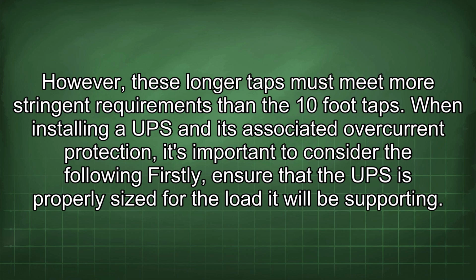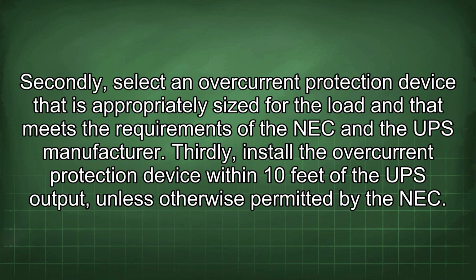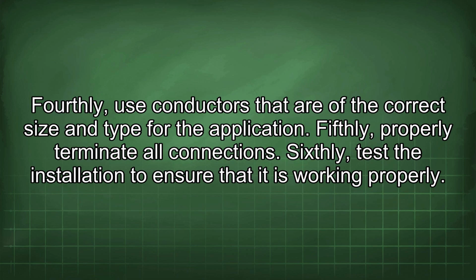When installing a UPS and its associated overcurrent protection, it's important to consider the following. Firstly, ensure that the UPS is properly sized for the load it will be supporting. Secondly, select an overcurrent protection device that is appropriately sized for the load and that meets the requirements of the NEC and the UPS manufacturer. Thirdly, install the overcurrent protection device within 10 feet of the UPS output unless otherwise permitted by the NEC. Fourthly, use conductors that are of the correct size and type for the application. Fifthly, properly terminate all connections. Sixthly, test the installation to ensure that it is working properly.